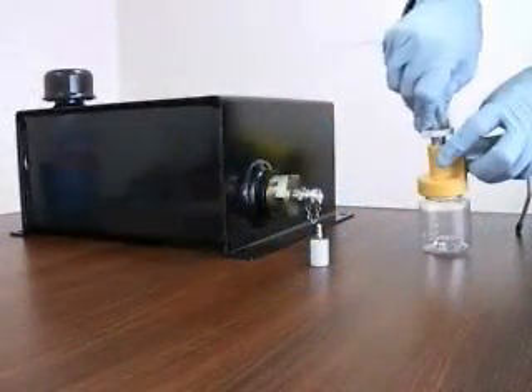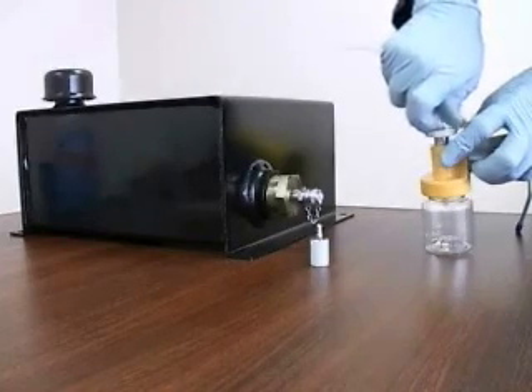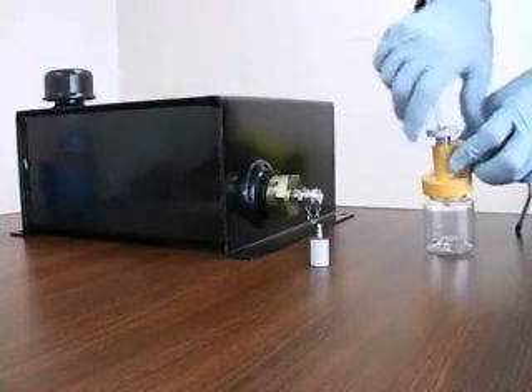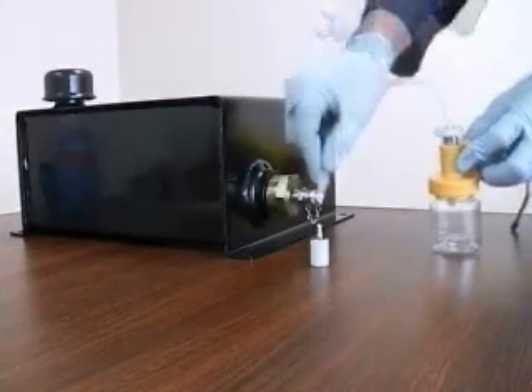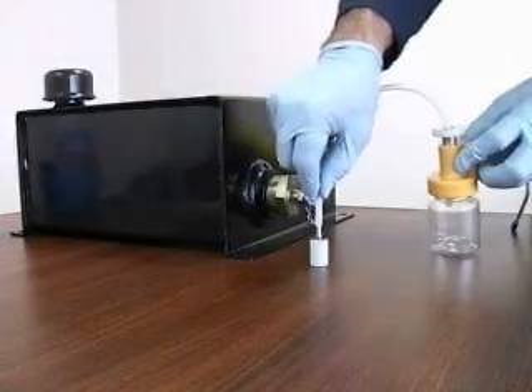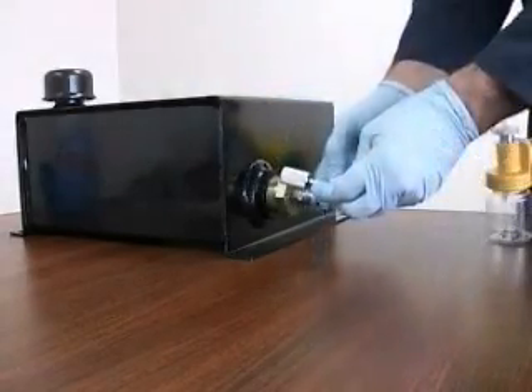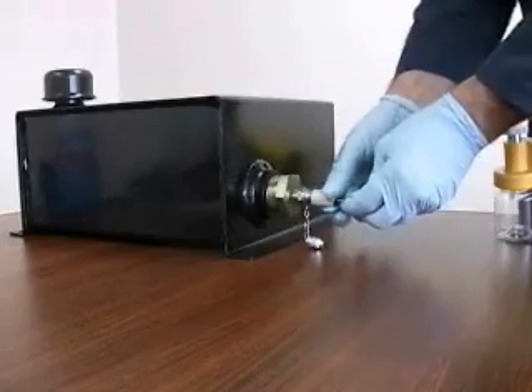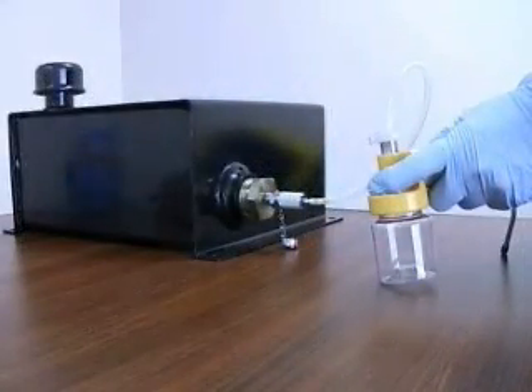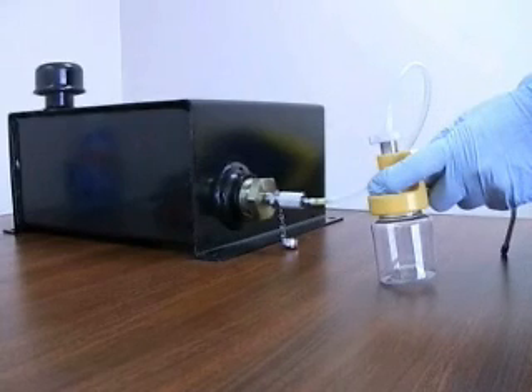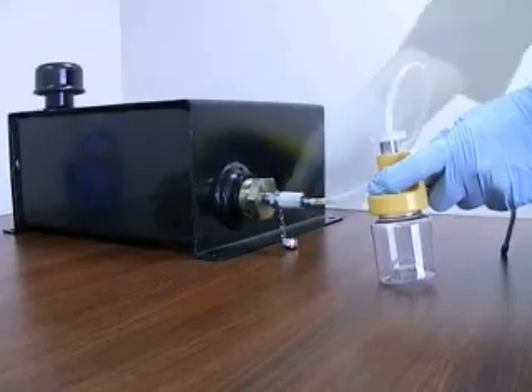Insert one end of the tube approximately 1/2 inch below the pump. Over-tightening will restrict the flow. Insert the other end of the tube into the probe. Next, uncap and attach the probe to the valve. Draw a purge sample to clear the static oil in the LT tube. The amount of purge oil is usually less than 2 ounces or 60 milliliters for an LT 24-inch.